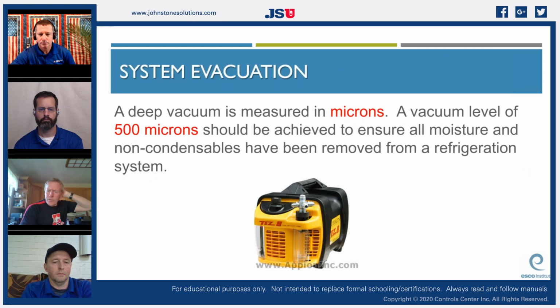Microns is how we check to see if we get the proper vacuum. We've covered this before, but usually 500 microns is acceptable. We would like to get lower than that. You can't over evacuate it, but depending on if you have clean oil and what the length of your line set is and a lot of other things, you should be able to get them down to 500 microns.